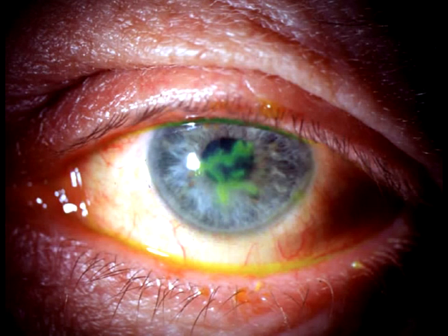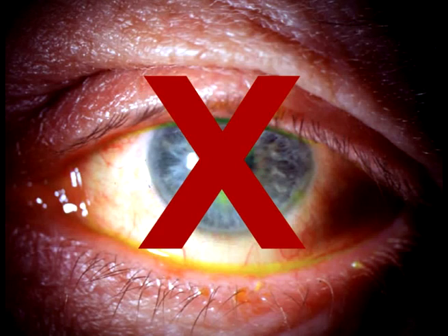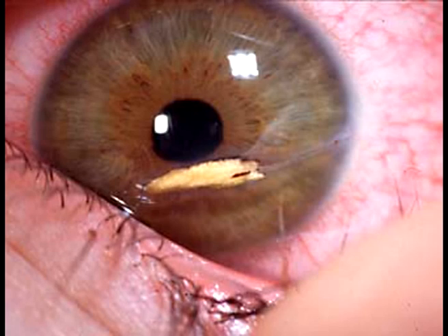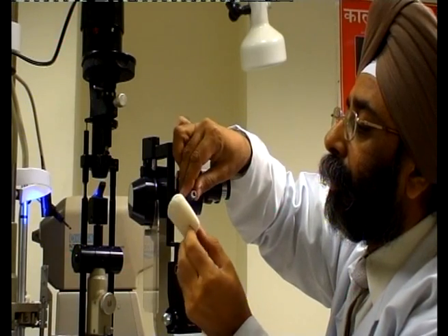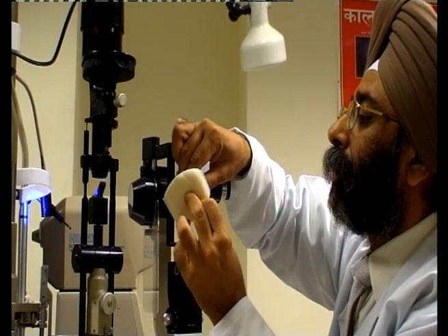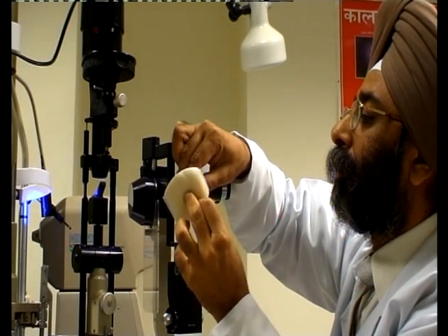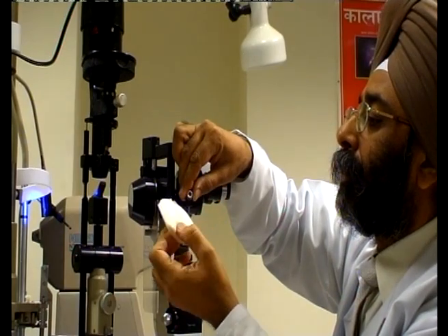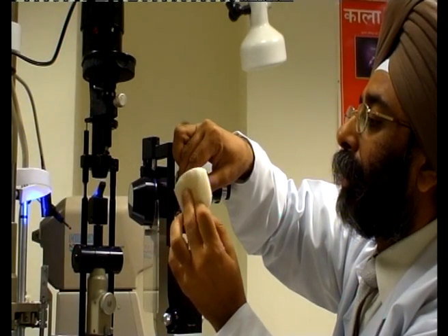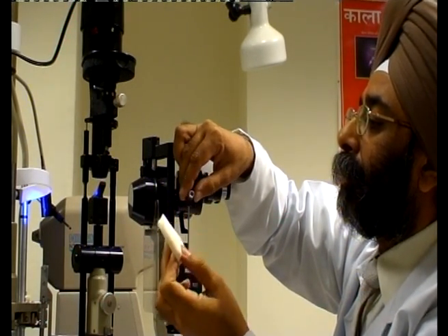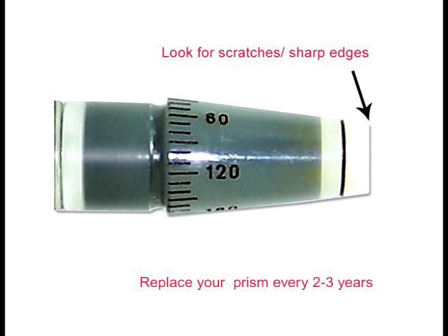Certain precautions need to be considered before undertaking the procedure. Contact tonometry should be avoided in infected or injured eyes. Remember to clean the tonometer between two cases and disinfect the prism after a day's use. Remove the chemical thoroughly after disinfection or cleaning. One should verify the prism for scratches and sharp edges when the day starts, and replace the prism every 2 to 3 years.